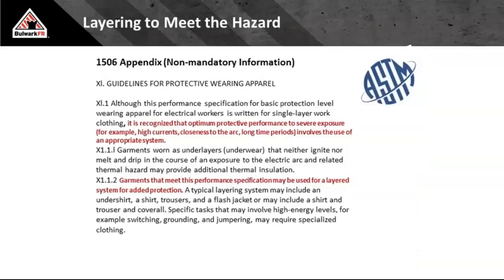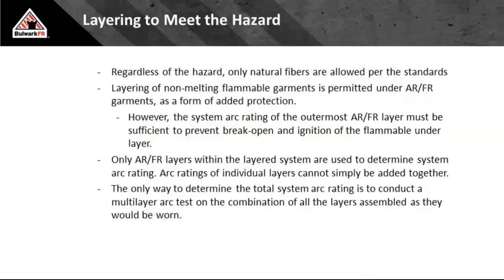Our standards even recognize that electrical workers many times are going to be up against more incident energy than their protective gear can perform to. So what does it tell you? Right there in the standards, it says layering up. NFPA 70E has a whole annex. Annex M walks you through how to layer up and protect your folks. Now, regardless of the hazard, only natural fibers are allowed under the standards.